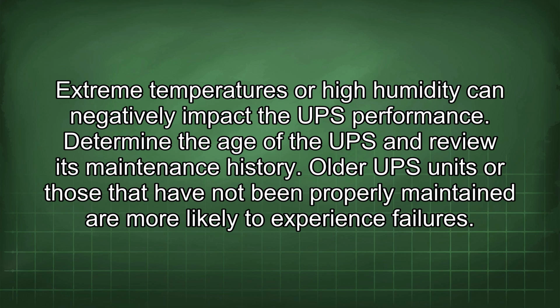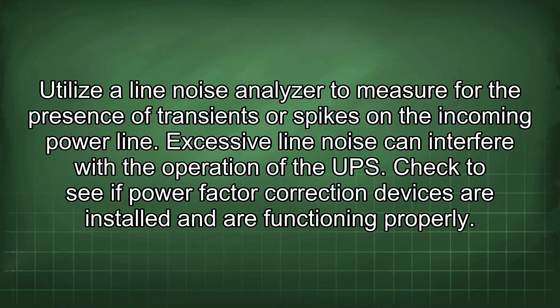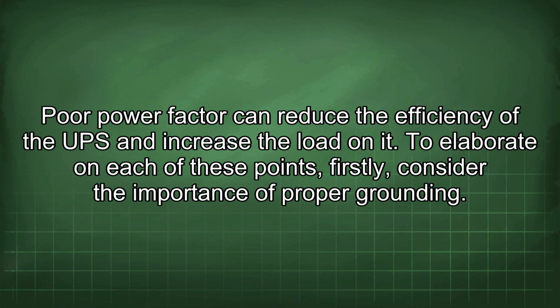Determine the age of the UPS and review its maintenance history. Older UPS units or those that have not been properly maintained are more likely to experience failures. Utilize a line noise analyzer to measure for the presence of transients or spikes in the incoming power line. Excessive line noise can interfere with the operation of the UPS. Check to see if power factor correction devices are installed and are functioning properly. Low power factor can reduce the efficiency of the UPS and increase the load on it.